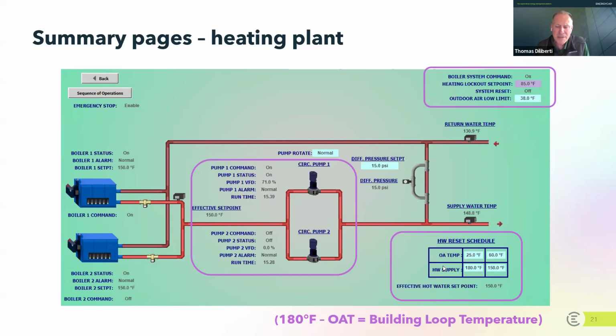So what that means is that the outside air, as it rises from 25 to 60 degrees, again, outside, it's going to allow the loop temperature to decrease from 180 down to 150. This adjustment in temperature is a huge energy savings opportunity for an organization. So if you are not making use of reset schedules, please take a look at that. And another way of saying this is this: if you always have the water at 180 degrees during the mild time of the year, so the spring and the fall, you are creating an awful lot of heat that is wasted.